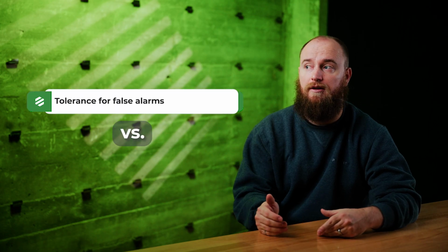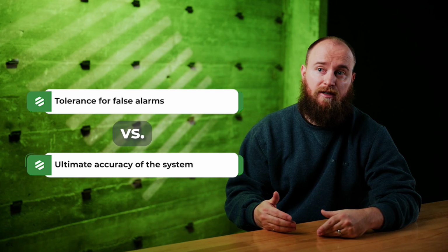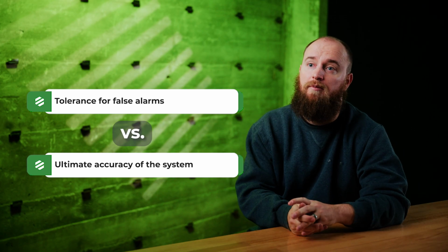Another important consideration in defining what we're trying to achieve on this pipeline is understanding the client's requirements in terms of their tolerance for false alarms versus their desire for the ultimate accuracy of the system. They operate in a bit of a teeter-totter, where more false alarms means that you will get ultimately better, or a smaller, minimum detectable leak size. Whereas if you have a lower tolerance for false alarms, then we will look for something slightly larger than meter accuracy, just so we can prevent those false alarms from ringing in.